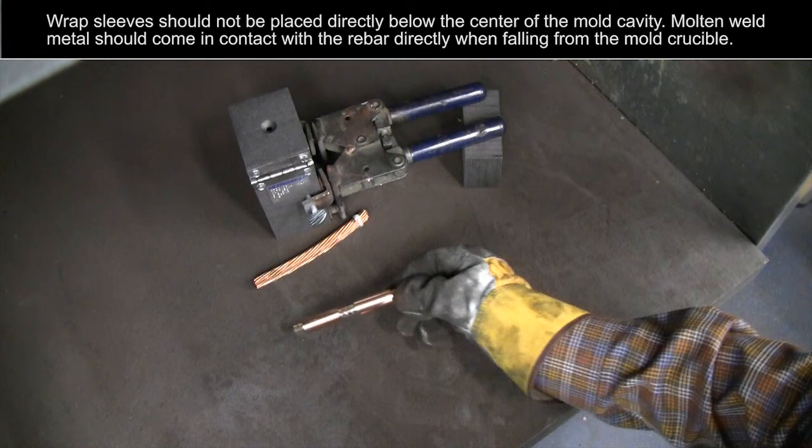Wrap sleeves should not be placed directly below the center of the mold cavity. Molten weld metal should come in contact with the rebar directly when falling from the mold crucible.